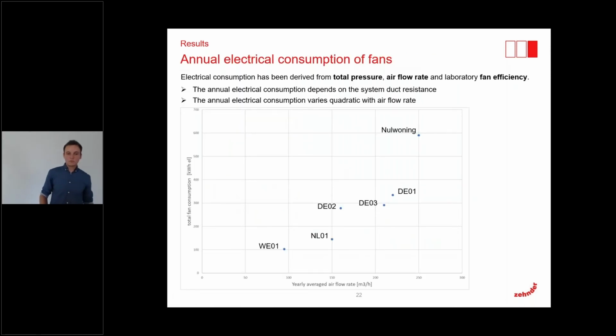So these were the energy savings, but now we also need to take a look at the energy we need to provide for these systems, which is mainly the electrical consumption of the fans. As you know, the electrical consumption of fans depends on the system duct resistance, and it also varies quadratically with the airflow rate. In the diagram, we can see the yearly average airflow rate of the 6 field units and the total fan consumption. We had 100 kilowatt hours per year up to 600 kilowatt hours per year in the Netherlands. This was the highest rate.